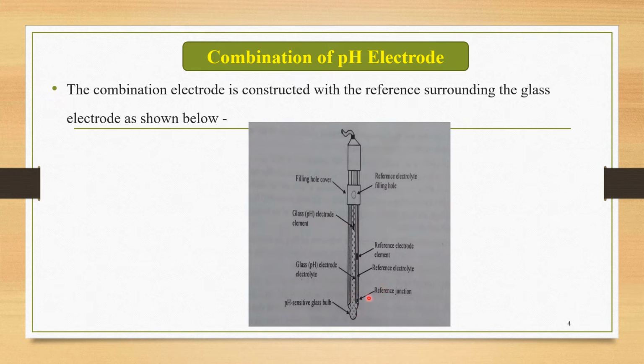This part is called the reference junction. The next part is the reference electrolyte. For this reference electrode, some electrolytic solution is there, so it is a reference electrolyte. The next part is the glass electrode electrolyte. Similar to the reference electrolyte, there is again a glass electrode electrolyte. The next important part is the reference electrode element. Next is the glass electrode element. These two elements construct the two different types of electrodes. One is the reference, the second is the glass.